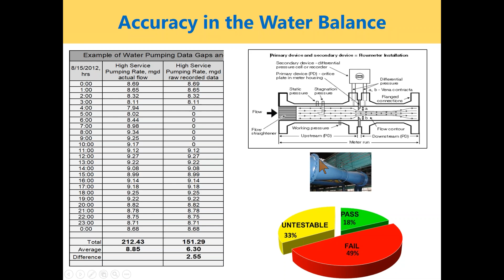They're two distinct activities. Both are important, but they are distinct. If you're only doing one, you have a limited understanding across the spectrum, because an issue like the one we saw is an issue in the primary device, where the primary measurement gets taken. It's not an issue at the secondary device, anything that a calibration would reveal.